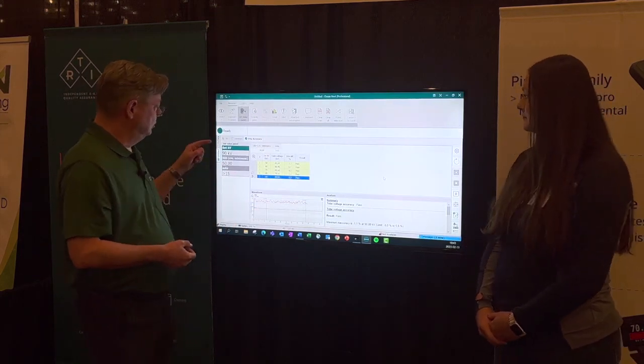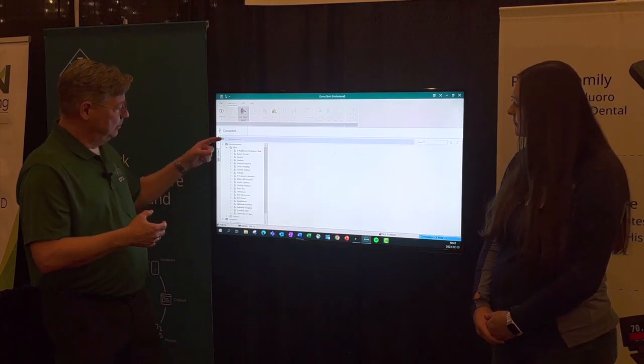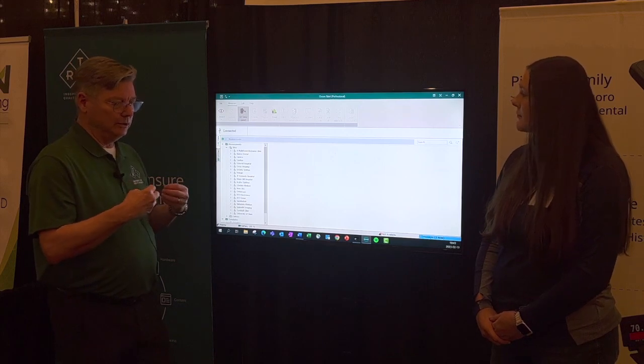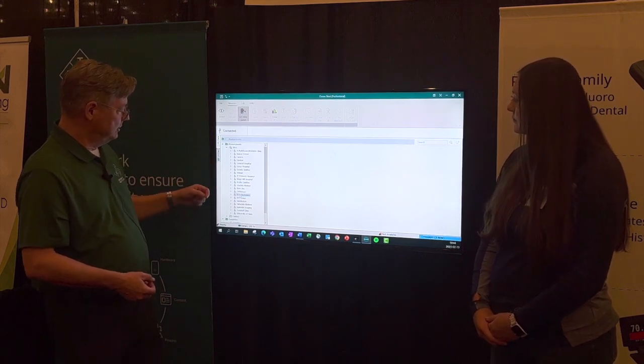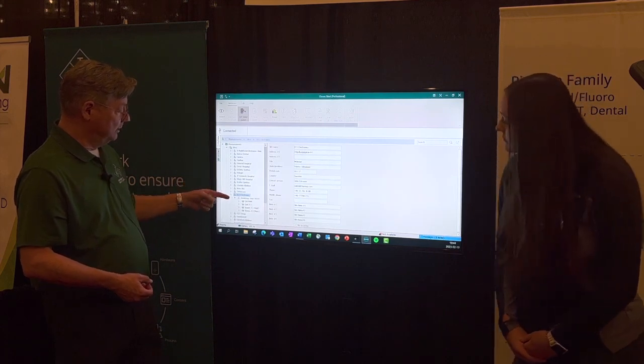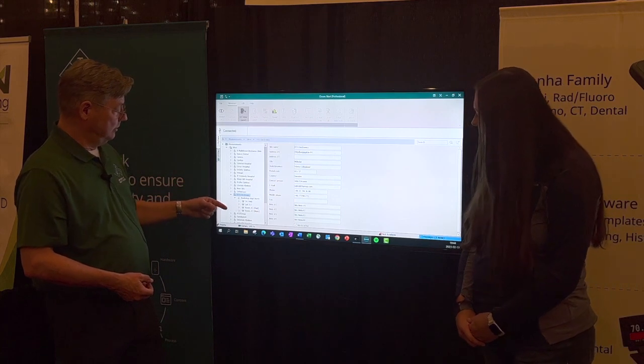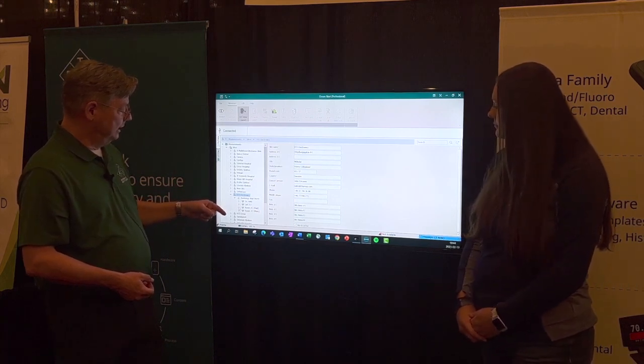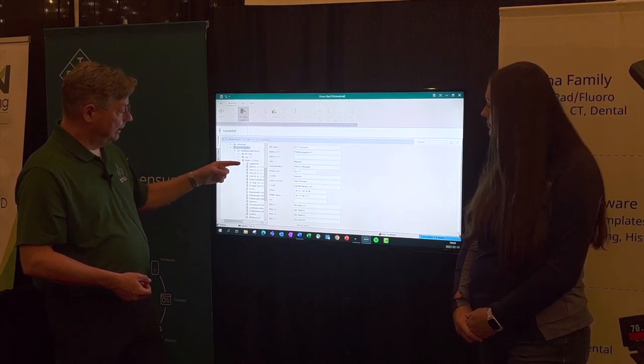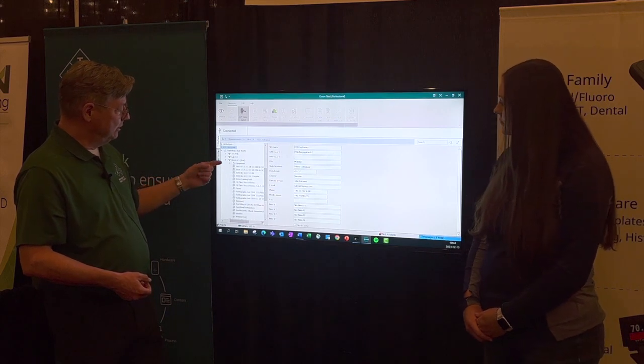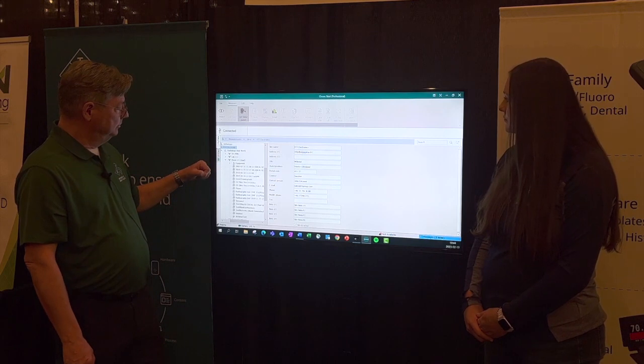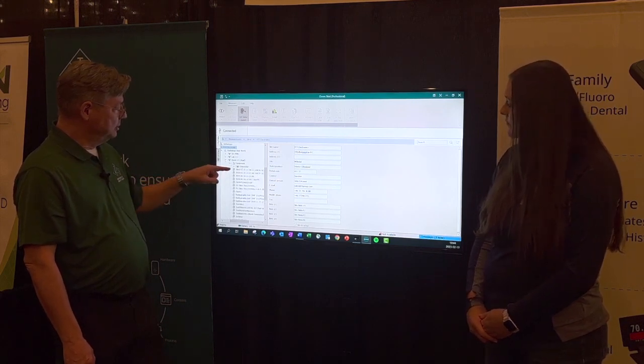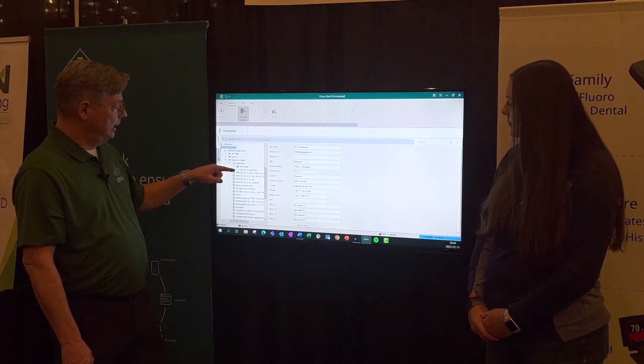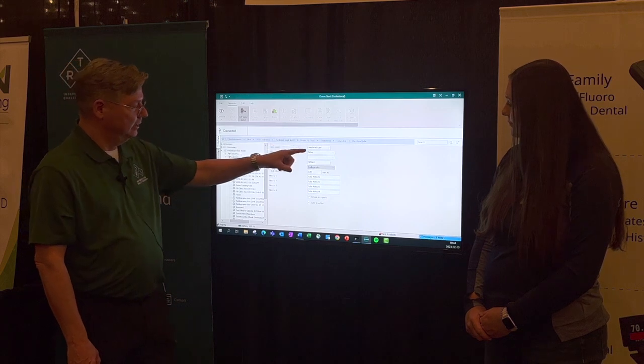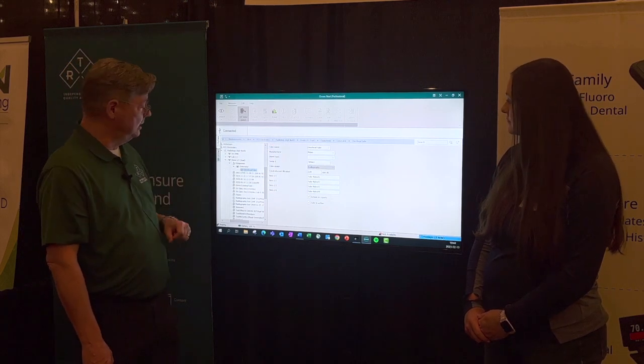Right, and it documents it. And if we go to the database, we'll see that we can build a database based on the customers we visit, or the sites that we are responsible for, where each of the sites, if we go into RTI Electronics, for instance, here, we have one or more departments. Each department can have one or more rooms, and in the rooms, room 1, for instance, I have a RAD room there. We can go in and have equipment, and that equipment can be a generator and a tube. So if we click on that, there we go, we've got a generator, and associated to that generator we have an overhead tube. And if we click on that, we'll see that we've entered and built a database with information about the tube, including serial number, manufacturer, and all that kind of stuff. Same thing with the generator.